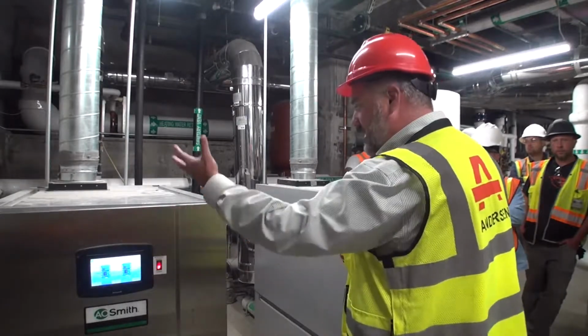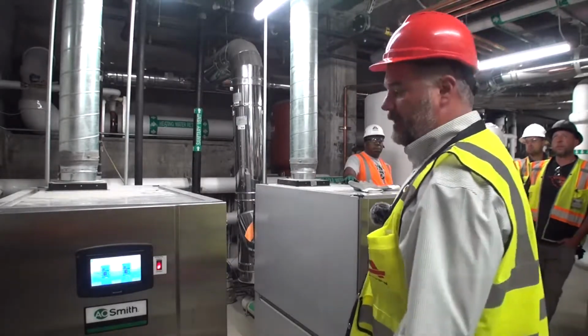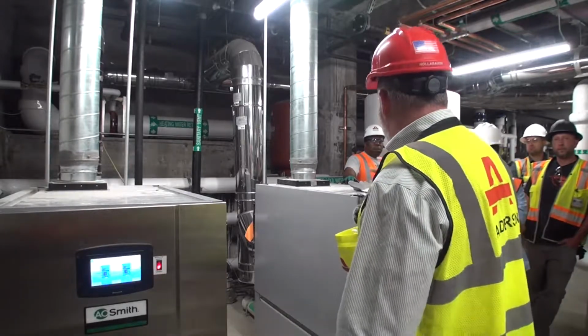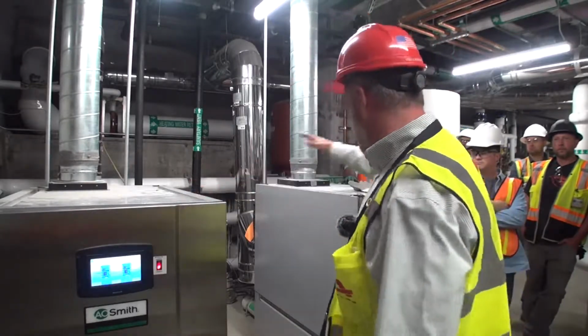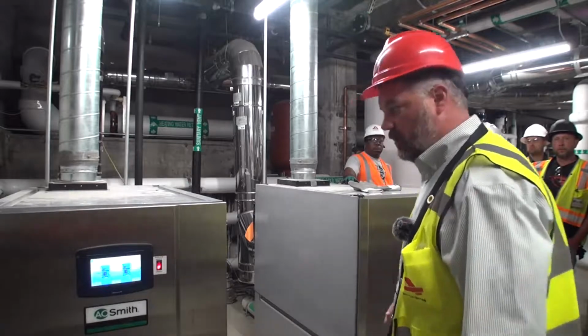If needed, they both can kick on if there's a very large demand, but the goal is to have a lead lag so that we're not just firing all at one boiler, firing all at the other boiler. We do want to have rotation going on.